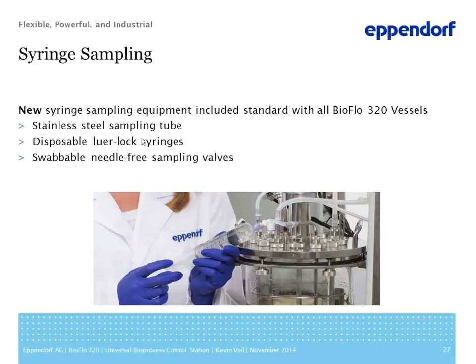One of the updates for us is a syringe style sampling. We've moved to this on all of our single-use products, and now we're starting to incorporate it on our autoclavables. It includes the sampling tube, which is very standard in the autoclavable vessel, but also a swabbable, needle-free Luer style connection for the syringe sampling device.